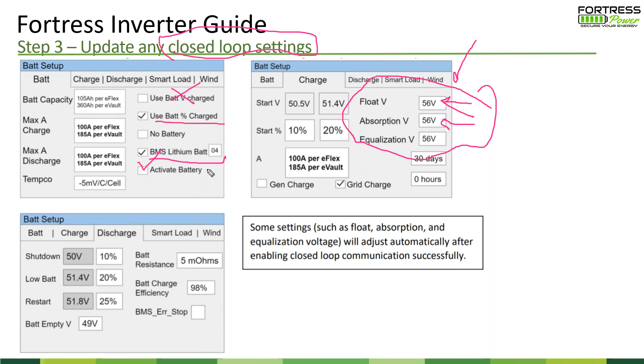When you have closed loop established, that's when you go back and take it off battery voltage mode and go into battery percent charge mode with a BMS04 activated, and you can do the activate battery feature as well. BMS04 is the communication that's needed for the Fortress batteries, both for the eFlex and the eVault. The communication is the same. The only difference is the wires that it comes out on the Ethernet jack between the two product models. We only support closed loop communication with the eFlex and the eVault. We do have another battery in our product line, the LFP series. The LFP series does not support closed loop communication. So these are settings that are just for closed loop communication.